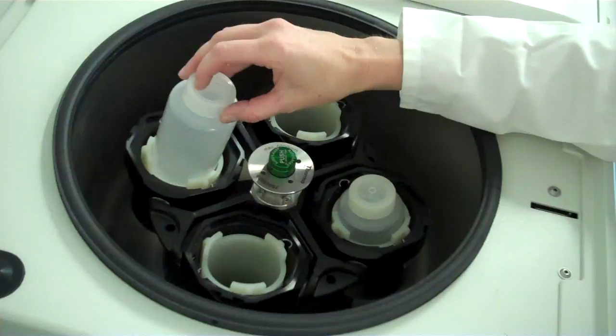Okay, when you balance a centrifuge, you place those bottles, as I said, opposite each other. If you put the bottles, for example, as shown here, that would lead to an imbalanced rotor and would perhaps permanently damage the machine upon turning it on. So once again, bottles must be balanced, that is, weigh the same with their caps, and balanced bottles that weigh the same must be placed opposite each other in the centrifuge.